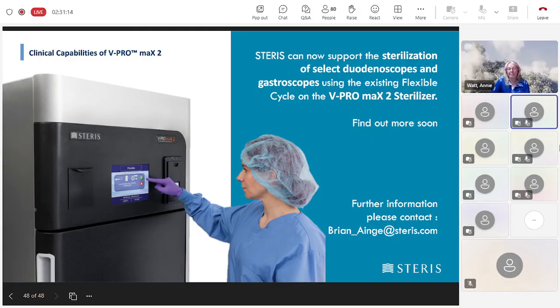Okay. Are there any other vaporized hydrogen peroxide sterilizers that are cleared to reprocess these devices? No. Meaning STERIS. Yeah, no. STERIS are the only low temp vapor hydrogen peroxide sterilizer that is cleared by the FDA with 510K to process 3D printed medical devices in the specialty cycle. To date, nobody else with a low temperature sterilizer has these claims.